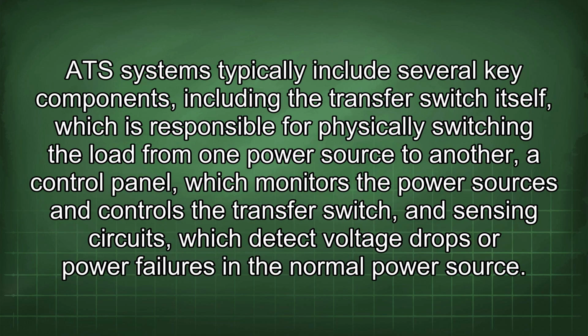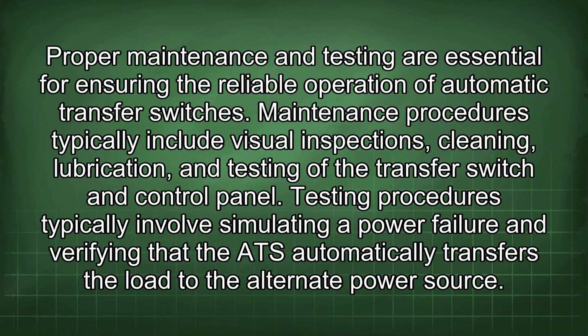ATS systems typically include several key components, including the transfer switch itself, which is responsible for physically switching the load from one power source to another, a control panel, which monitors the power sources and controls the transfer switch, and sensing circuits, which detect voltage drops or power failures in the normal power source. Proper maintenance and testing are essential for ensuring the reliable operation of automatic transfer switches.